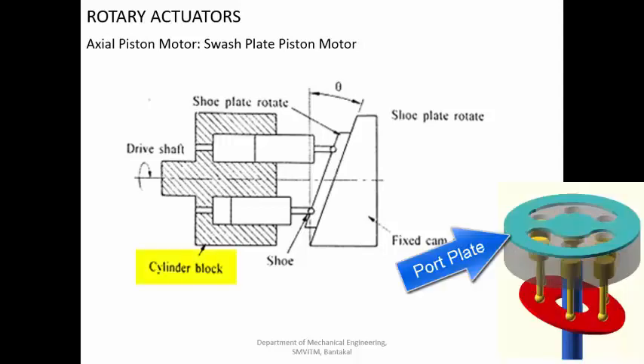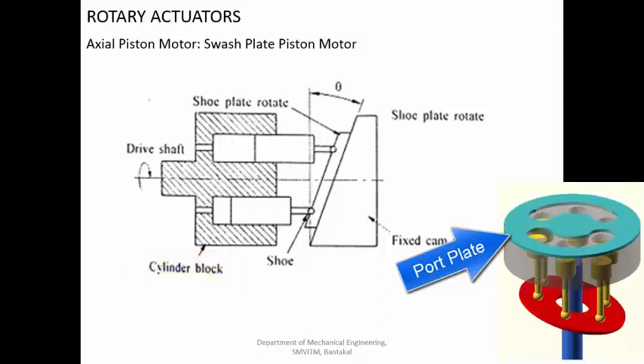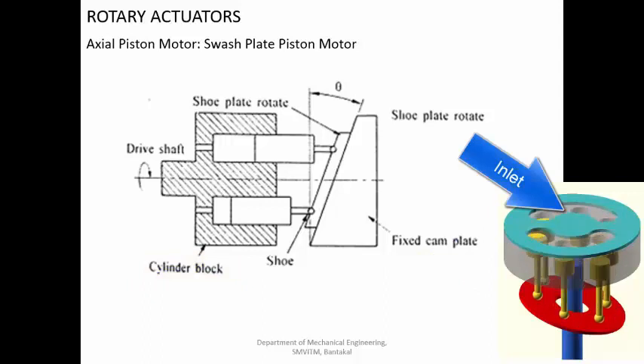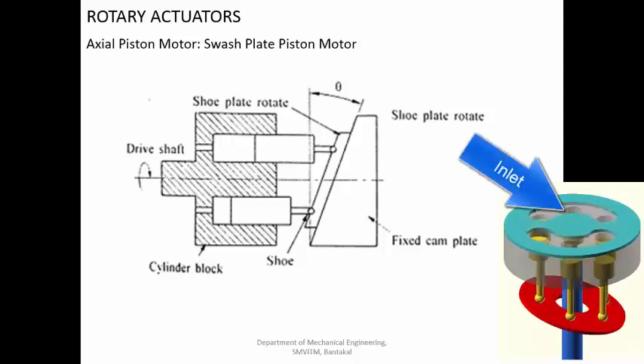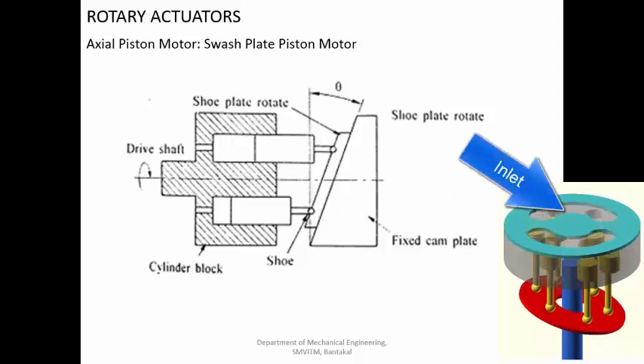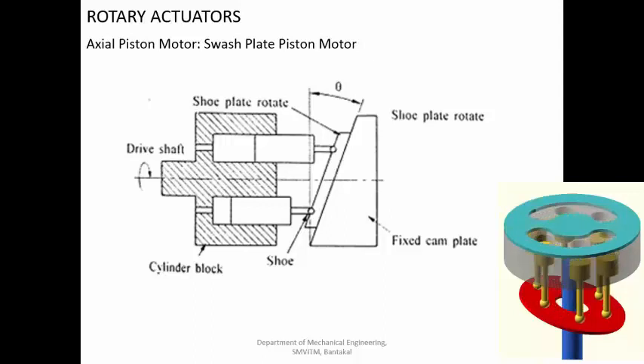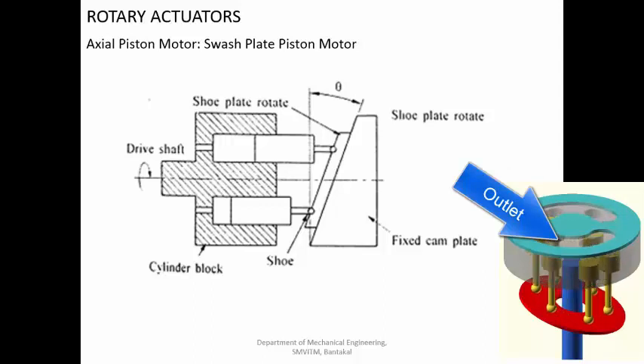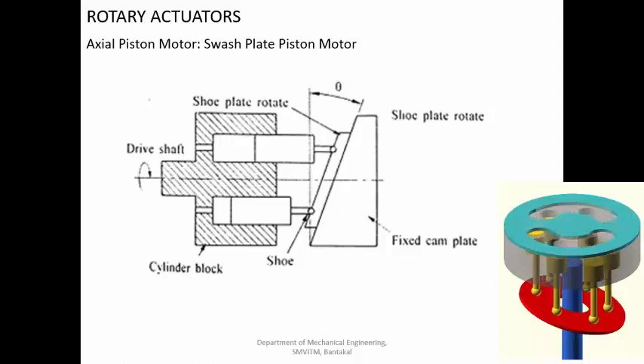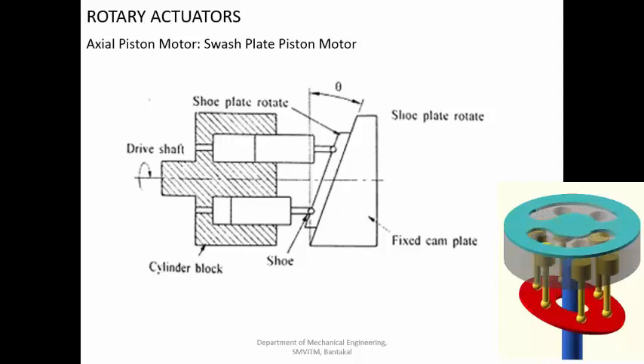This is the cylinder block. Here you will have a port plate. You will have an inlet port which will be in an elliptical shape. Simultaneously, high pressure fluid is entering into several pistons and the oil that is escaping out goes into the outlet port over several pistons. Maybe three or four pistons are covered simultaneously through the outlet port, and three or four pistons are simultaneously covered through the inlet port, giving you the continuous motion.